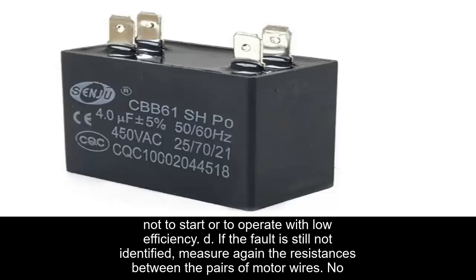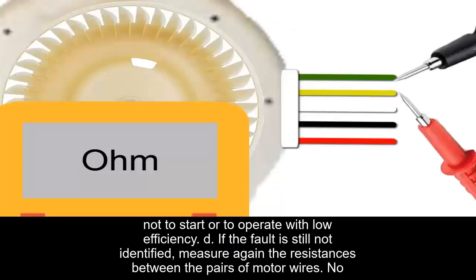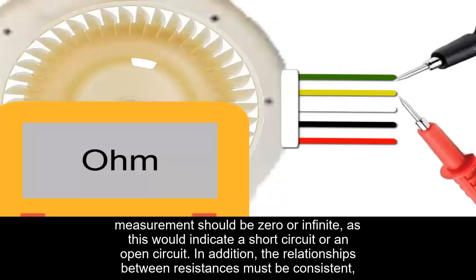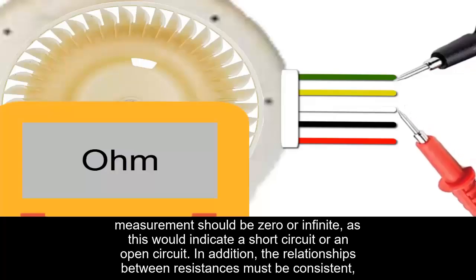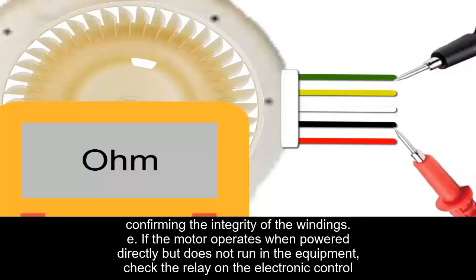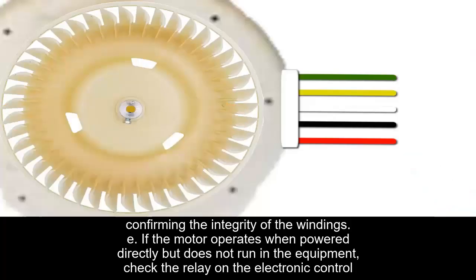D. If the fault is still not identified, measure again the resistances between the pairs of motor wires. No measurement should be 0 or infinity, as this would indicate a short circuit or an open circuit. In addition, the relationships between resistances must be consistent, confirming the integrity of the windings.